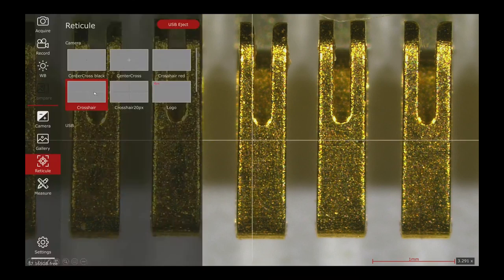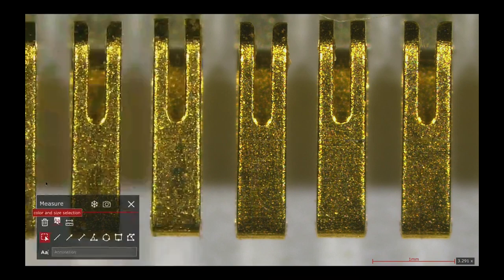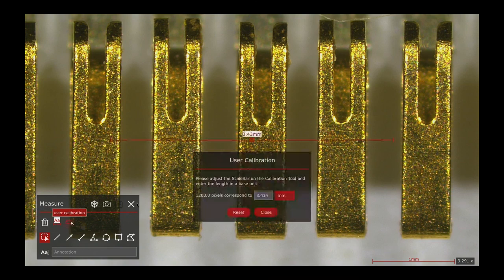The next menu button we are going to use is measure. And if you click on measure, automatically this user interface appears. And in measure, you have different options. One option, which is very important if you want to control if the measurements are correct, is to check if the user calibration is correct or not. This is very easy. You put a scale, an object micrometer underneath, adjust the line, and then check if the number of pixels corresponds to the distance that you've just shown or try to measure. And then you can say here, reset, and give in the number yourself.